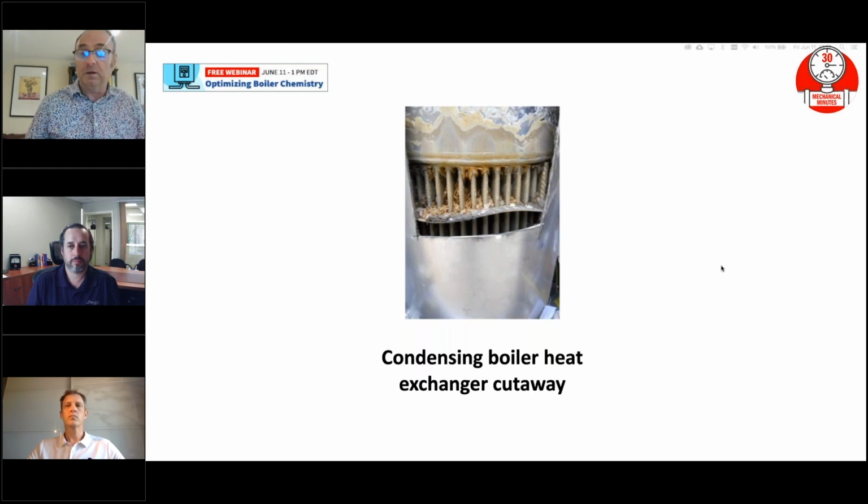The other thing I'm seeing in a large commercial building is that your water has a certain amount of minerals per million parts. In a soft water system, like you showed in the manual there, it says what the acceptable level of hardness is. Well, you could install a boiler in a building and test the city water and say, okay, city water is fine, it's within those limits, so you think you're fine. The problem is there might be so much volume in that building that over time there's enough mineral content in that volume of water, even though the water itself is within acceptable limits. The total volume brings so much calcium into these heat exchangers that you're still going to have a problem. And I've seen that happen as well.